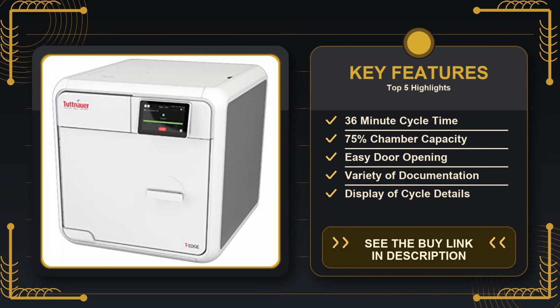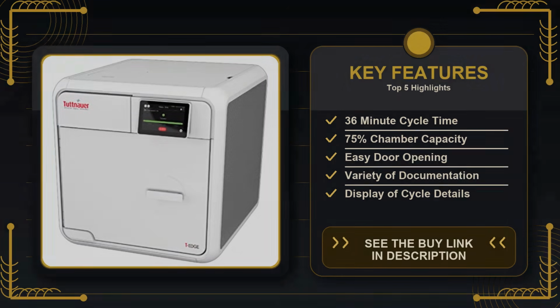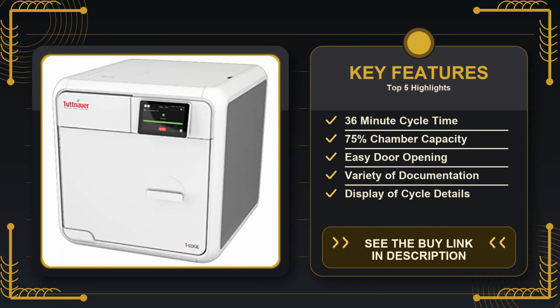specific instrument requirements. Another hidden expense to consider is the water consumption. Autoclaves rely on a steady water supply, and the EDGE10S monitors levels on its screen, alerting you when it's low. The unit doesn't have an internal reservoir large enough to sustain multiple cycles without a refill, so you'll need to plan for a water source nearby. In practice, this isn't an issue for a clinic with a sink on the same countertop, but for a mobile lab or a field.